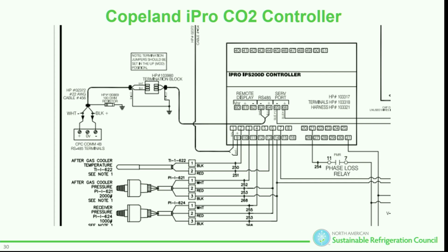And that's why we have to deal with the same thing with the case controllers. You can see here where my temperature probes are, they've got to be wired properly and to the right location. And believe it or not, if the screw I tied them into is loose, I have a bad input, yes? Sometimes, especially temperature probes on the drop leg, it can come loose. If I look at one of these controllers and I see the temperature popping, I don't change the probe. First thing I do is check and make sure it's tight. Check and make sure it's tight. Understand, start simple. What Brett's saying I love: KISS. What does KISS stand for?